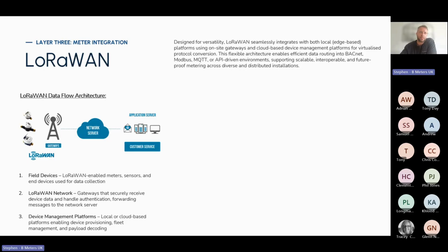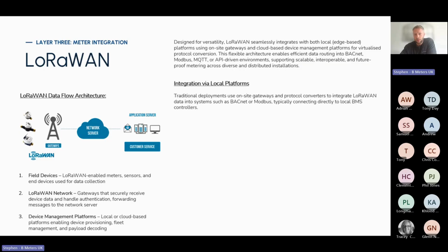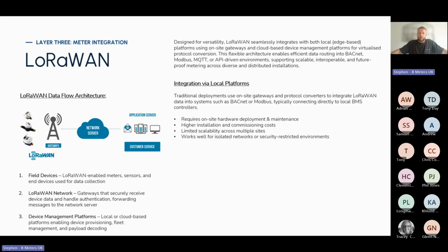For example, the Milesight UG67, UG65, UG56, they all have onboard network server. So integration via local platforms requires on-site hardware deployment and maintenance. They do have a higher installation cost in terms of hardware and commissioning cost, and limited scalability across multiple sites. It does work well for isolated networks or security restricted environments, and it's often necessary for legacy BMS systems. So a typical local integration would be using either the MileSite or the WattSense integration hub, where you have multiple meters.